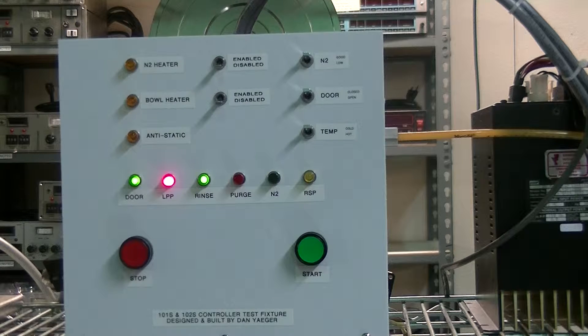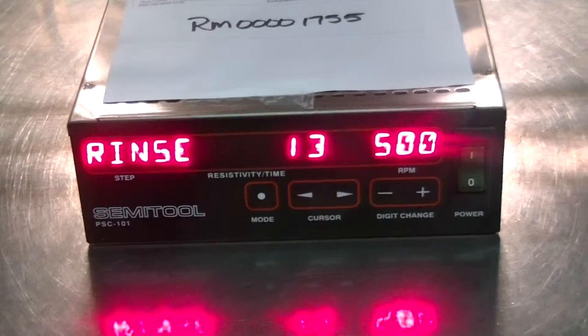This is mimicking your rinse process of your SRD recipe. As you can see, we're on rinse, counting down 15 seconds, stable 500 RPMs, everything you're looking for.